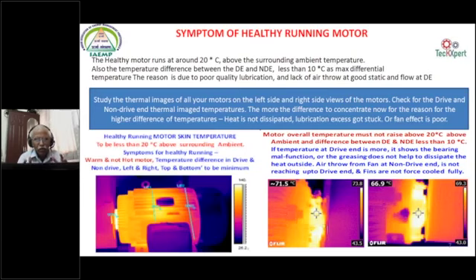A typical motor manufacturer says my motor can withstand up to H class insulation, F class insulation. That's all okay. But as I told before, at the start of the webinar, let us go back to the basics of the energy conservation law. Whatever input is given to the system, here a motor, whatever kilowatt I am giving to the motor, that same kilowatt should be deliverable at the output shaft. That is the motor input-output relation. If the output shaft delivery is going less and the losses are going more, heat is a symptom of loss. So automatically the motor gets heated and overloaded. So look into heat as a symptom, hotspot as a symptom, then you can definitely correct it.